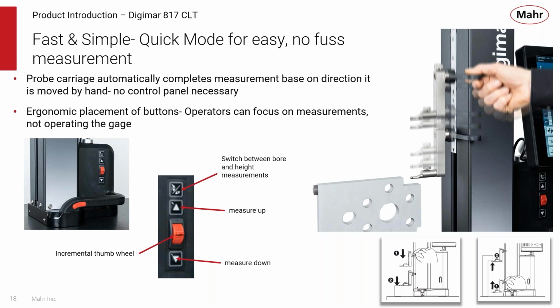These include up and down measurement buttons, so if you bring your part close to the 817, you can hit the down or up arrow and it'll move in that direction to make a measurement. There's also a button to toggle between simple bore and height measurements, and an incremental thumb wheel for driving the probe carriage up or down - the further you push it, the faster or slower the carriage moves.